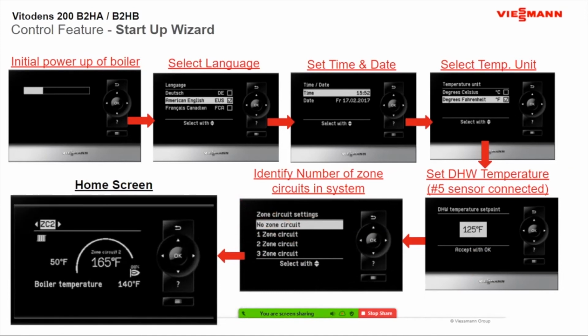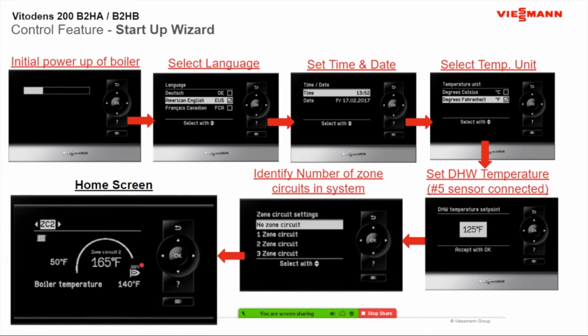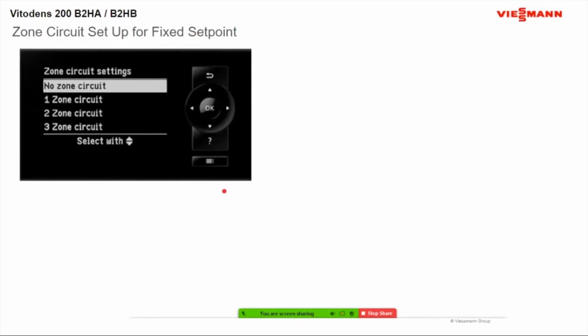If you're doing zone circuits and you pushed 1, 2, or 3 zone circuits, this would be the screen that would come up. So you would go from here to this style screen. This is more of the startup wizard feature that's on this boiler here. This is where it's going to take those end switches and thermostats. You can still see here we're set up for what the boiler temperature is, but it's still set up for outdoor temperature here. If you're doing a fixed set point, you will not see your outdoor temperature. We'll talk about that a little bit. So we're going to just show you an example. When you first start up the boiler, for this one here, we're going to pick 2 zone circuits for an example.